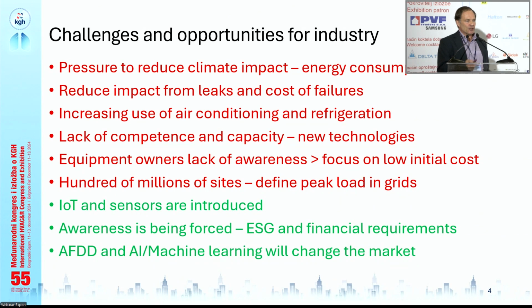So I'm not going to go into the details of the internal method. I would say that it's extremely well proven. I patented the method in 1986, but it is basically pure thermodynamics. The only trick is that you need to realize that you can make the compressor a mass flow meter by using the energy law: if you put energy in, it has to come out. So if you know the enthalpies and you know the power that goes into the compressor, you actually know the mass flow of refrigerant. So it's very straightforward.